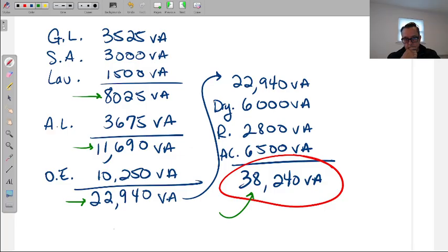For the small appliances, how do you get that number again? Two of them at 1,500 each. Okay, so small appliances is 1,500. Yes, 1,500 mandatory for each. And laundry circuit is one of them and also 1,500. You said OE is which one? That is the other equipment, such as garage door 750, spa 9,500. So the range is 28.